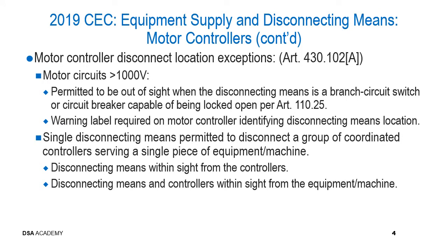Let's start talking about some of the exceptions for motor controller disconnects as identified in Article 430.102A. And the exceptions are the exception to having the motor disconnect or the motor controller disconnect within sight of the motor or the motor controller. The first is for motors that exceed 1000 volts. The disconnect is permitted to be out of sight when the disconnecting means is a branch circuit switch or a circuit breaker capable of being locked in the open position in accordance with Article 110.25. Additionally, a warning label is required on the motor controller identifying the actual location of the disconnecting means.